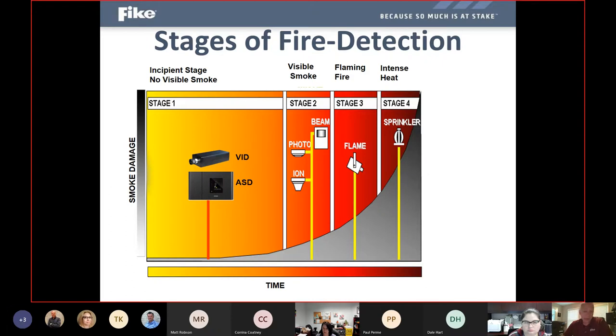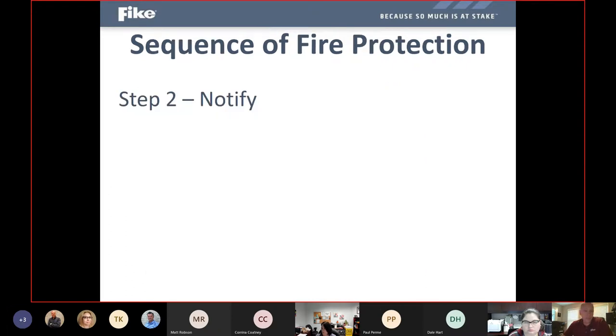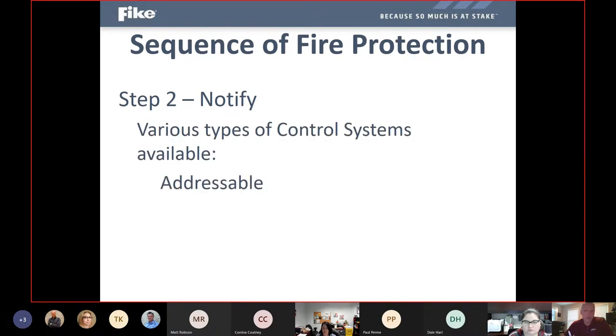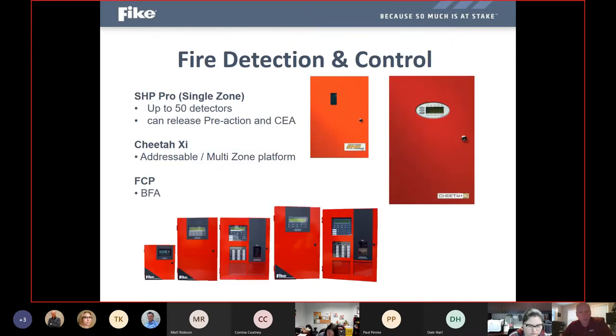And now the shorter portion of the presentation here is, we've detected, what are we going to do to notify people about it? Well, when it comes to control panels, we basically break them down into two types. You've either got addressable or single zone / conventional type control panels. And Fike does have a very wide product line for whatever size or complexity of the hazard we might have. Everywhere from a single zone conventional panel that's maybe just looking at up to 50 detectors in a small area or a relatively small complex that can still release either a pre-action sprinkler system or a clean agent system.